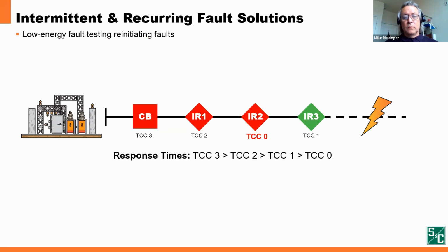Next slide. So we tested for the fault presence. IR3 was open, so we did not detect the fault. Because we don't know whether there might be a tree limb in between IR2 and IR3, we're going to remain closed for a selectable period of time, maybe 2 seconds, 3 seconds, operating on the fastest TCC we have, TCC 0. Next slide.